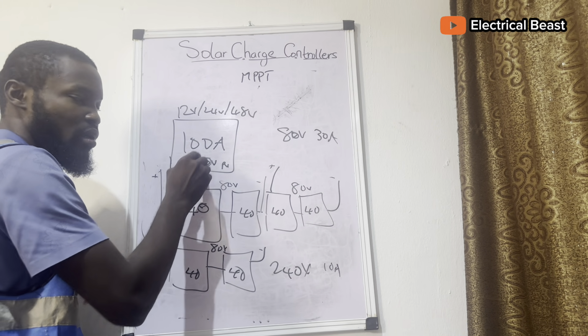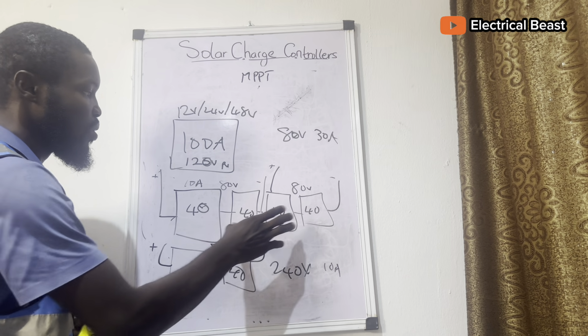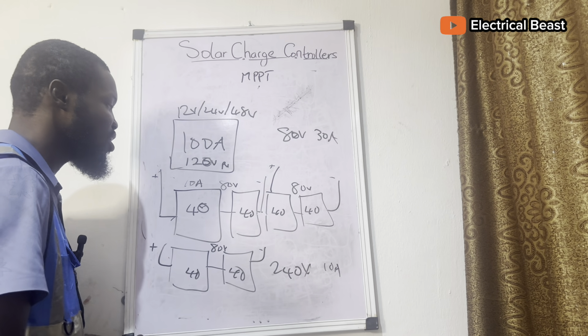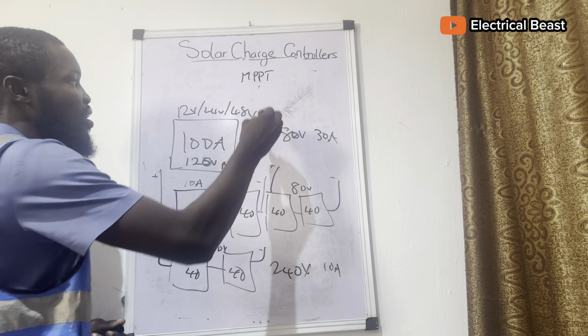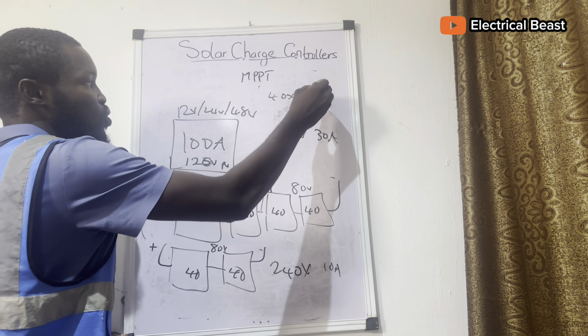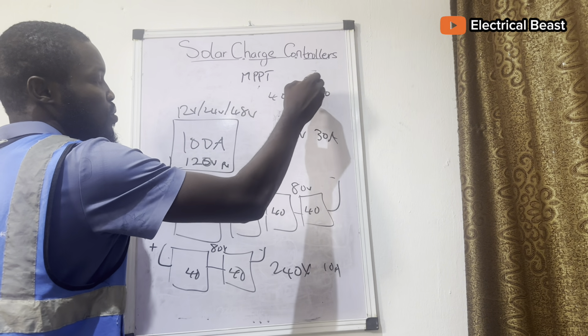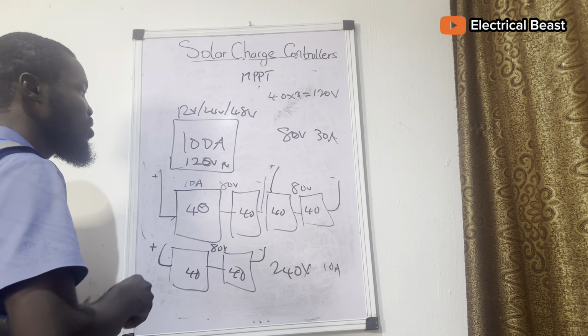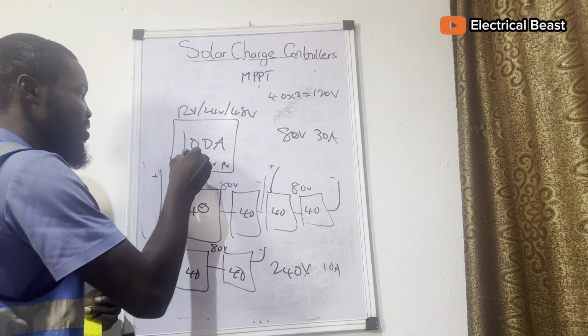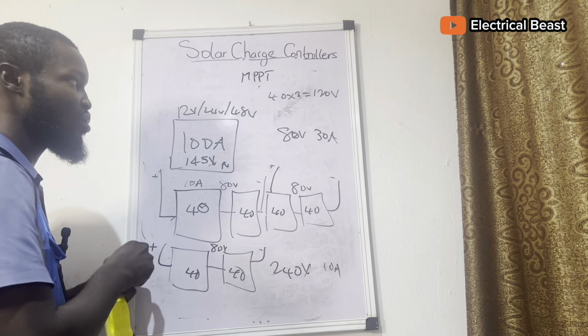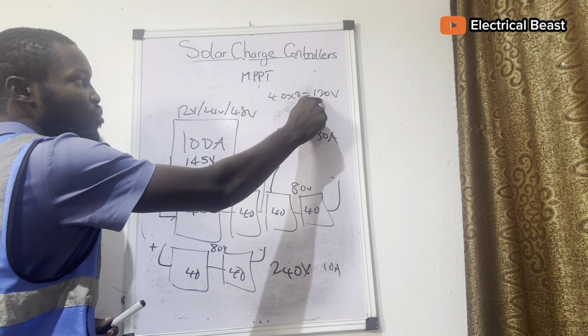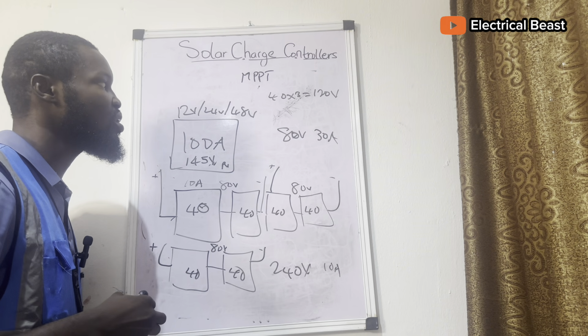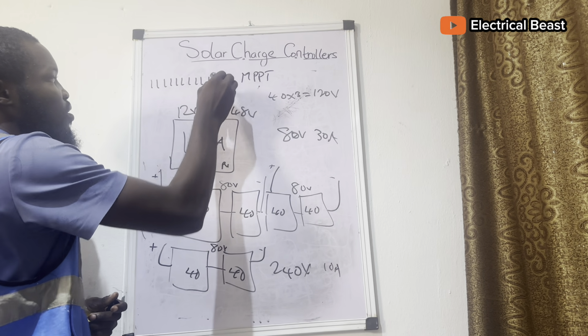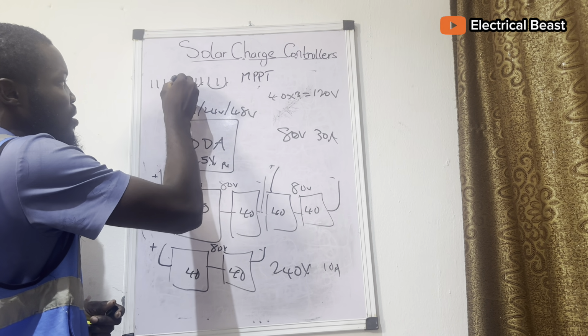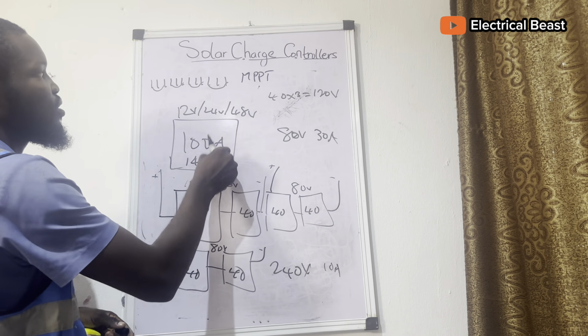It's within the safe range here. So it means you can even connect up to 12 panels. If you have 12 panels, you can connect three in series. When you have three in series, you have 40 times 3, which is 120 volts. Let's assume your controller right now is 145 volts. So when you connect three in series, you have 120 volts. If you have 12 panels, 1, 2, 3, 4, 5, 6, 7, 8, 9, 10, 11, 12, and you connect three in series, three in series, three in series, three in series, it means you are going to have 4 parallel connections, 1, 2, 3, 4.